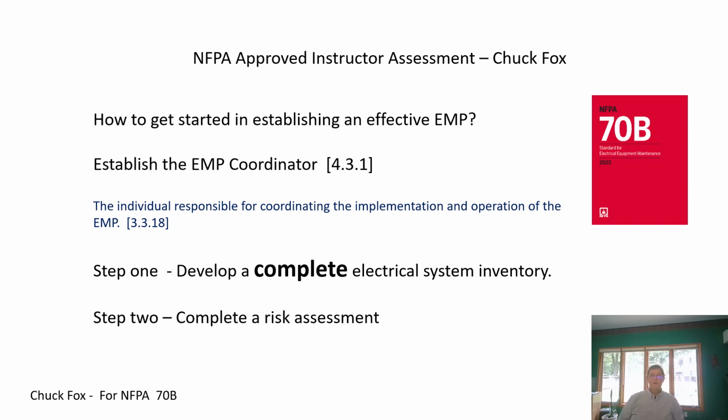To develop the program itself, there's a 6-step process that we can weave into the standard itself. And the first order of business of that is to develop a complete electrical system inventory and then embellish that inventory with the various aspects and requirements of the complete risk assessment, the various other studies and such, and additional requirements of data elements needed to do an ongoing management of the electrical maintenance program.